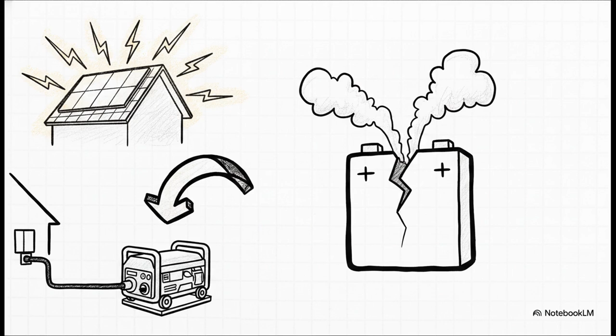Now, what's really interesting about this is that the hazards you face aren't strictly electrical. You've got unearthed PV arrays that can cause capacitive coupling, meaning the metal roof itself can give you a nasty shock, potentially causing a fatal fall. You've got incorrectly installed batteries presenting fire, explosive gas, and chemical hazards, and generators backfeeding through detachable connections. You are working in a multi-hazard environment every single time.